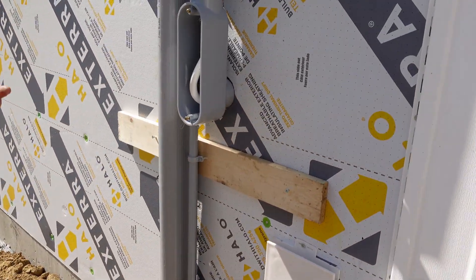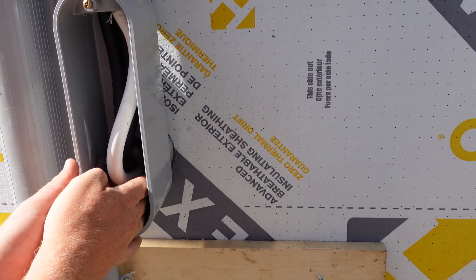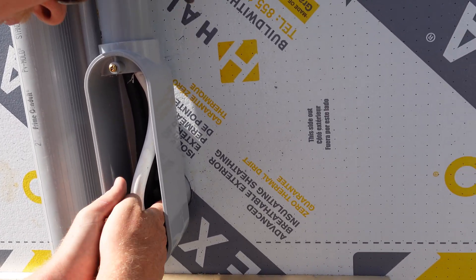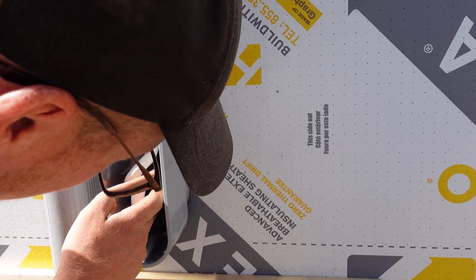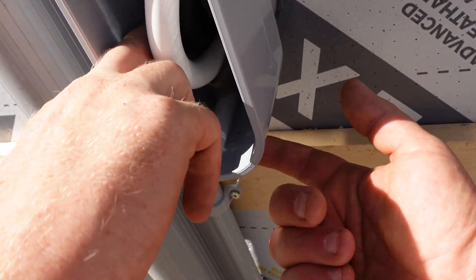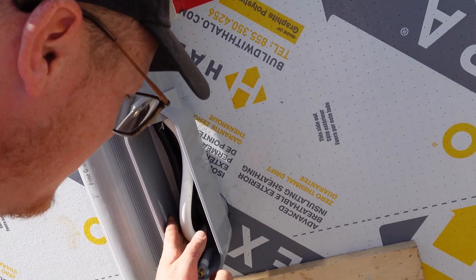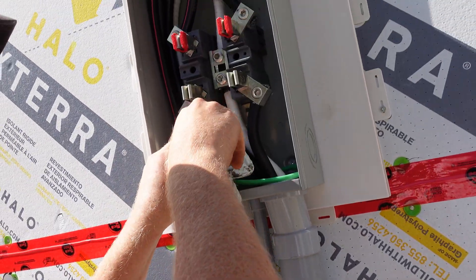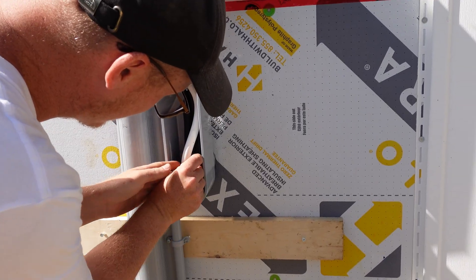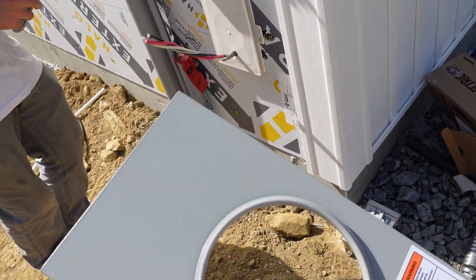Back outside, Luke is applying duct seal — that gets put right inside that hole and smeared around to keep moisture out. That's what we have to do here in Canada, and the inspector does check for it. We also have to have two small drain holes in the bottom, just to let water escape before we put the cover on.